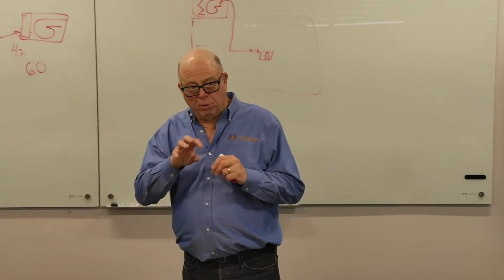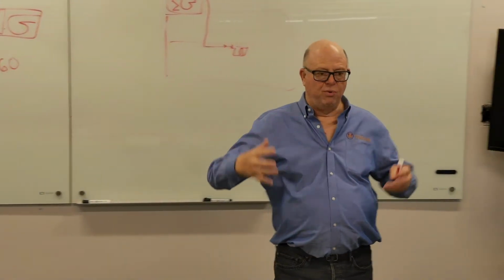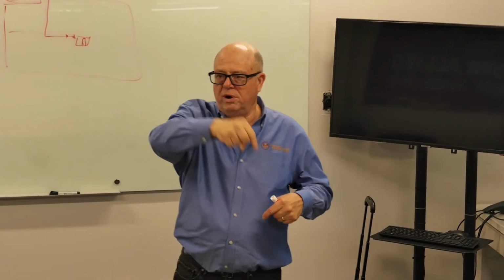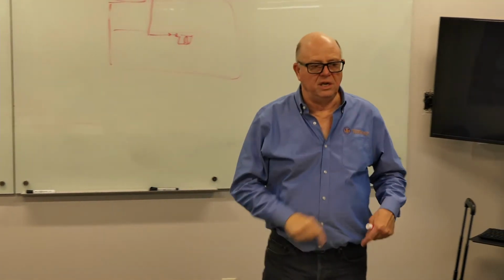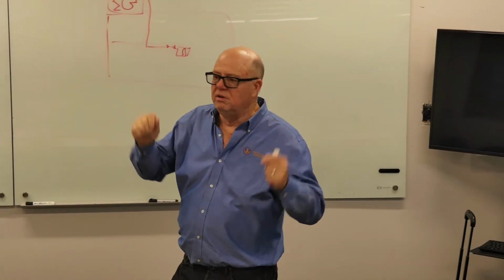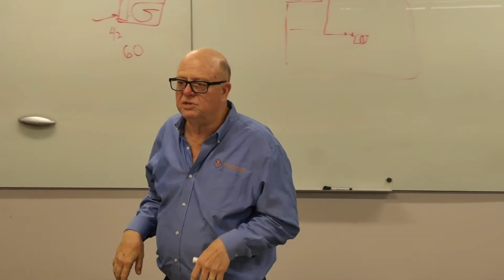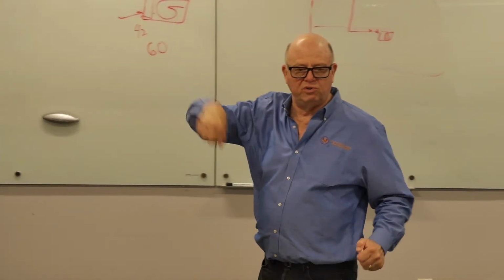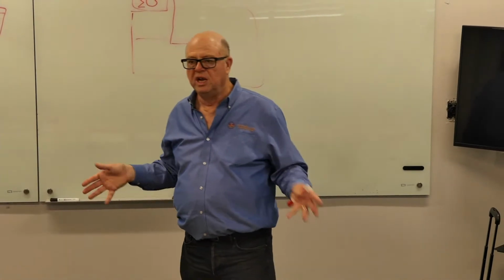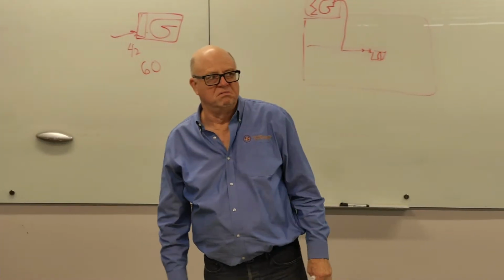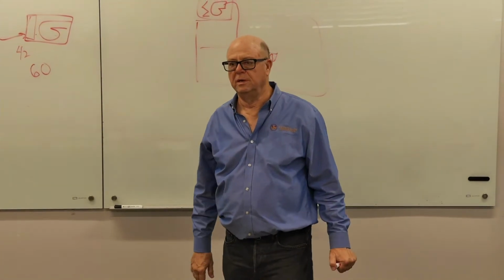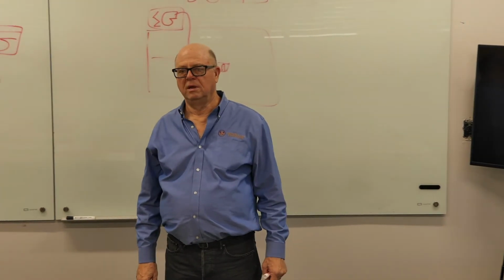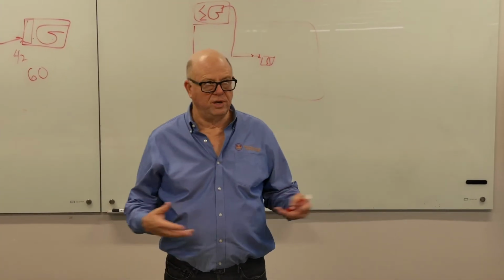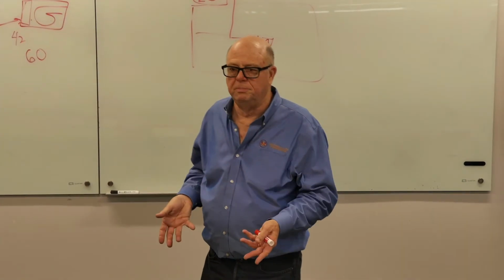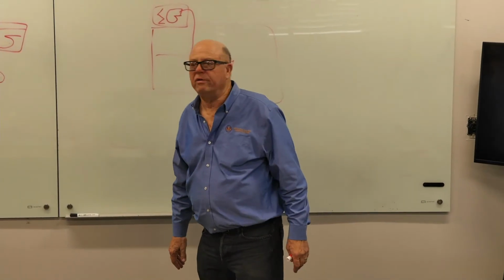And we ended up having to program about 3 at a time, doing that for like 10 or 15 minutes, moving around the station so that each fan coil spent 10 minutes, 12 minutes, 15 minutes in full dehumidification mode and then switched back to normal operation, just to keep the humidity level down somewhere between 50 and 60%, which is probably muggier than somebody who's a native here would think was acceptable for sleeping. Maybe if you get the room cool enough.